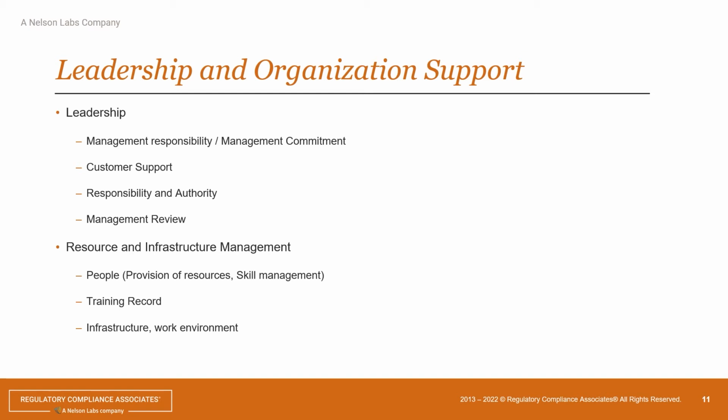Leadership, this should not be any surprise for anybody that has done ISO 13485 or is compliant with 820, and this is all about management responsibility, customer support. It's about management review, making sure that your quality system is healthy, and then you look at the totality of your system.